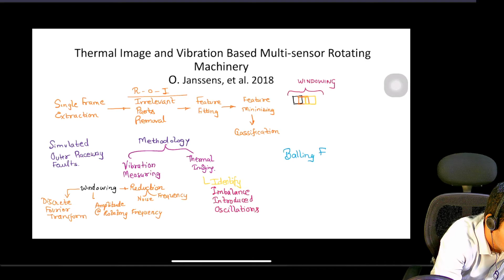For vibration measuring, they are doing windowing and using the discrete Fourier transform, taking the amplitude at rotating frequency and trying to reduce the noise in the frequency. Thermal imaging is to identify imbalance-introduced oscillations. This is a term in rotating machinery for ball bearings and fault detection systems. They find the main features to be kurtosis, crest, root mean square error, and ball pass frequency of outer raceway fault. Raceway damage will cause a peak at the bearing fault frequencies, and that is what they're trying to locate.